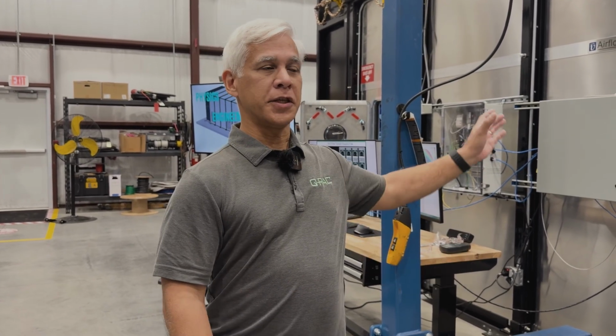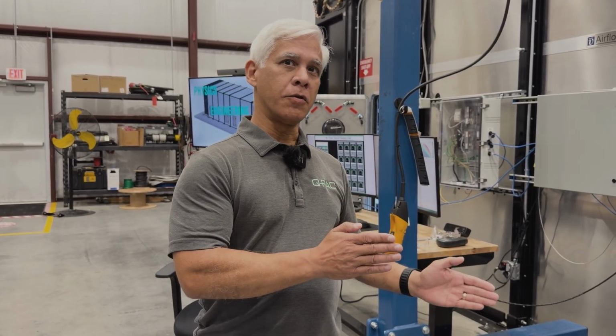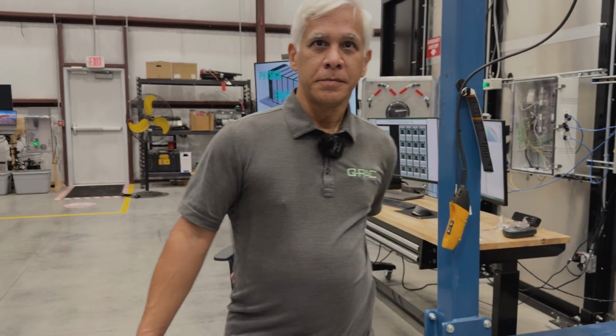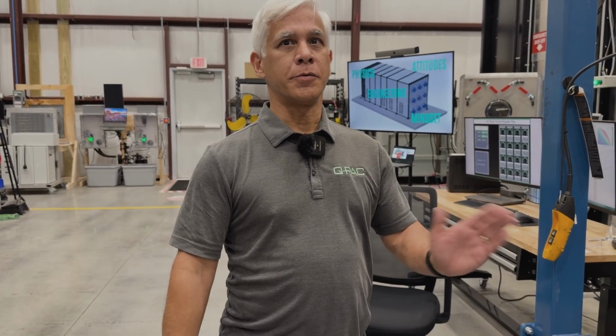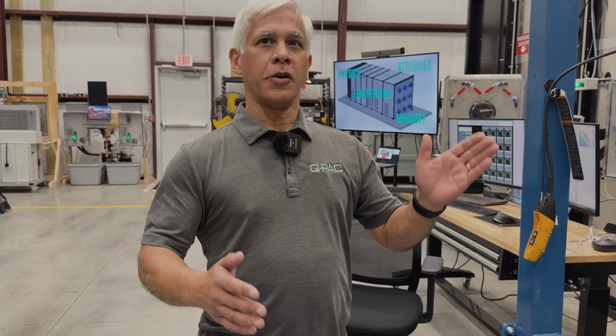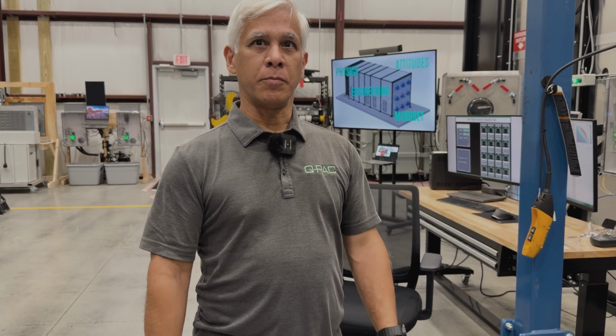So if we're blowing at atmospheric pressure here, we actually have to have negative pressure on the inside of the fan. So most of the time, for most of the testing, we will actually have negative pressure in the airflow tunnel. Because again, we only want that pressure difference: lower on the intake, higher on the exhaust side. And higher, because we're blowing into the air, is always going to be basically zero pressure. And with negative pressure in the airflow tunnel, we wouldn't expect to see any difference between that and a real life application. From a physics point of view, it is absolutely the same thing. In the tunnel, you're always worried about pressure difference. You're not ever worried about absolute pressure.